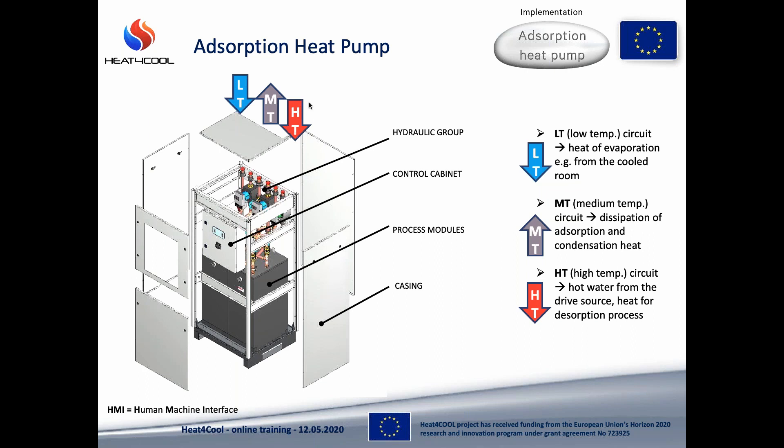HT has to be connected with a source of heat, for example solar collectors. MT is the heat dissipation circuit — this one may be connected with a dry cooler, wet cooling tower, swimming pool, or underground heat exchangers. Basically anything where you can dissipate heat at proper temperature levels.